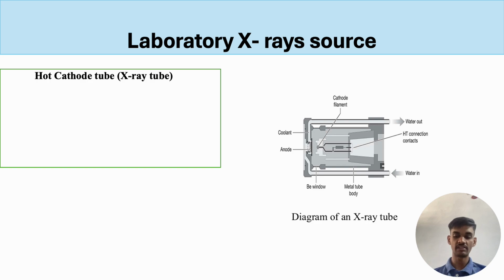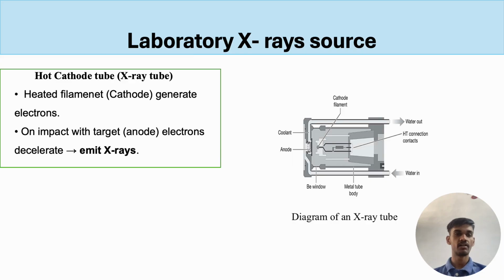An X-ray tube contains a heated filament that generates electrons, which are negatively charged, and it acts as a cathode, and the target that is a positively charged anode. When the electrons strike the target, X-rays are generated. At higher voltage, high energy X-rays are generated, and at higher current more X-rays are emitted by the anode and the X-rays become brighter.